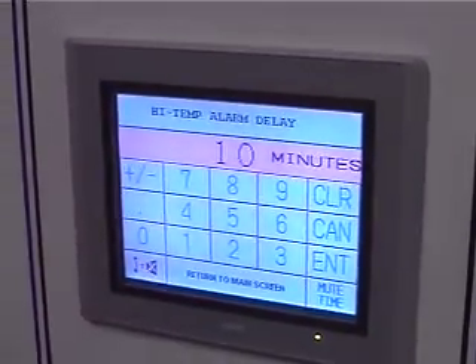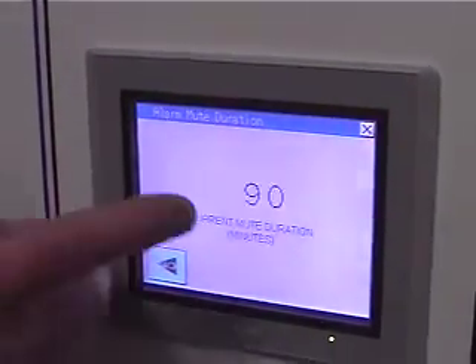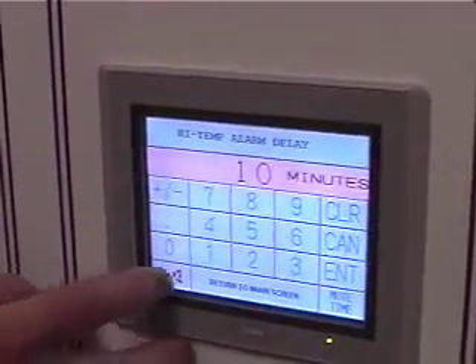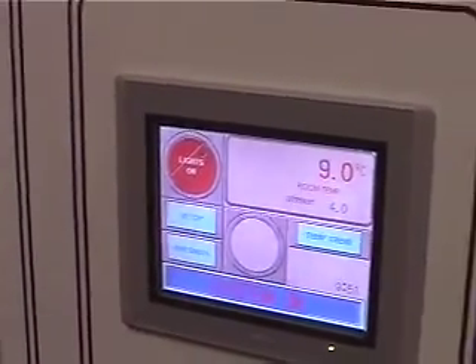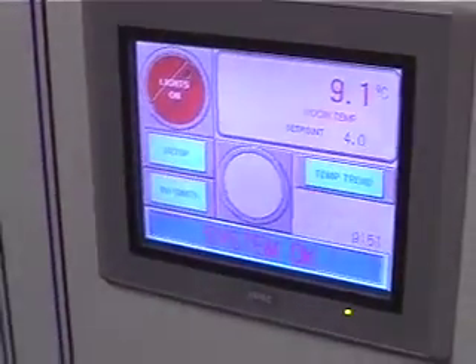The delay, there's your delay time, 10 minutes. We have several screens that'll take you to what's called mute time, and you can see it's mute. This is another one where you would set it up. What mute time does, let's go back to the main screen. If you go into alarm, the typical alarm on this, not the PEA, is a 1 second pulse, so you have that 95 dB, 1 second on, 1 second off. It's loud, but it's almost manageable. This little button will light up red and tell you you're in alarm. Press the mute, and you can hear it's an active alarm. It'll turn off the audible alarm and leave it in the state it is now. Mute time is you have 90 minutes to fix that problem. Otherwise, you have to come back in and touch the button again, because your horn's going to drive somebody crazy. That make sense?